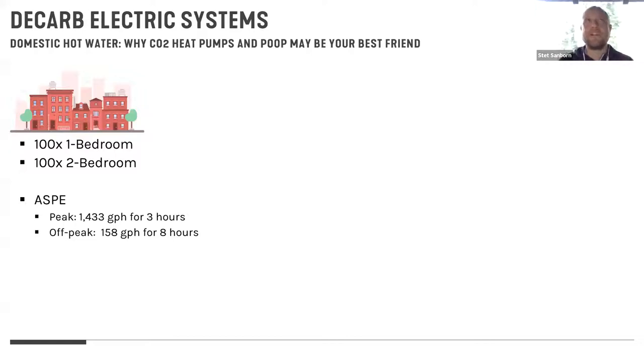The recovery, the ability for a heat pump to actually hit your peak load demand, if you size the heat pump to do it yourself, it will never be cost effective unless there's a radical change in cost structures around heat pump manufacturing. So it's always paired with storage. And what we've found is that the cost effective sweet spot is typically making sure that our BTUh available from our storage is about equal to what we can get from our heat pump. That tends to land out at a pretty cost-effective solution on our projects.